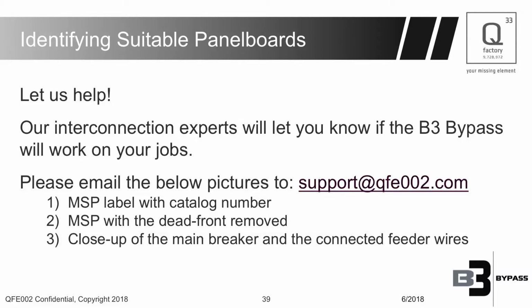we need 3 pictures. One of the catalog number of the main panel, so we can make sure it's on our compatibility list. Secondly, a picture of the main panel with the dead front removed. We want to make sure that it's wire fed, not busbar fed. Thirdly, a close-up of the main breaker to make sure that we have enough room, unbent wires, so we can attach it. So we ask, please send us these pictures. We'll review it. We don't need an address. We don't need any customer contact information. All we need is the main panel information. And then we'll give you the go or no go on that job.